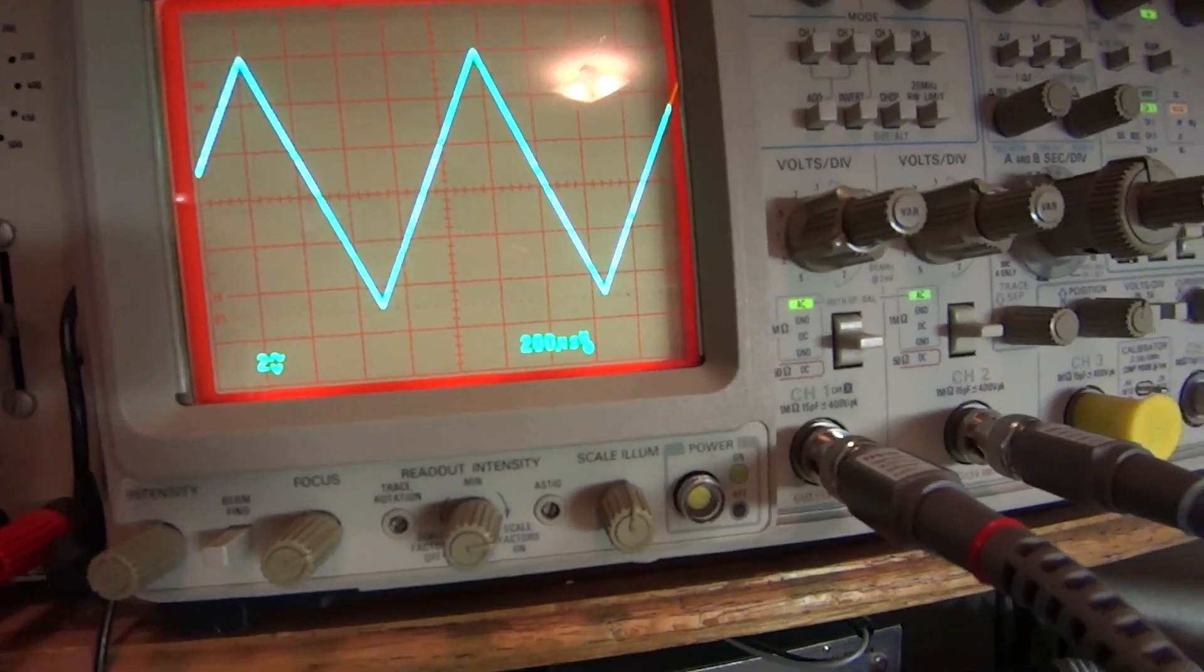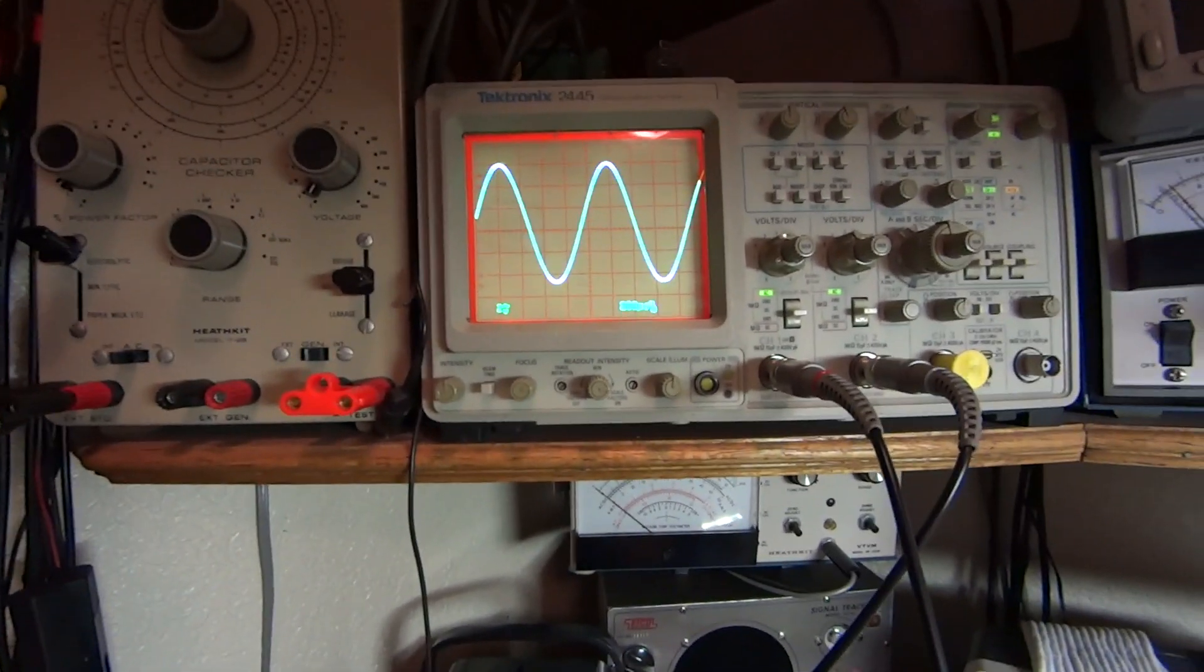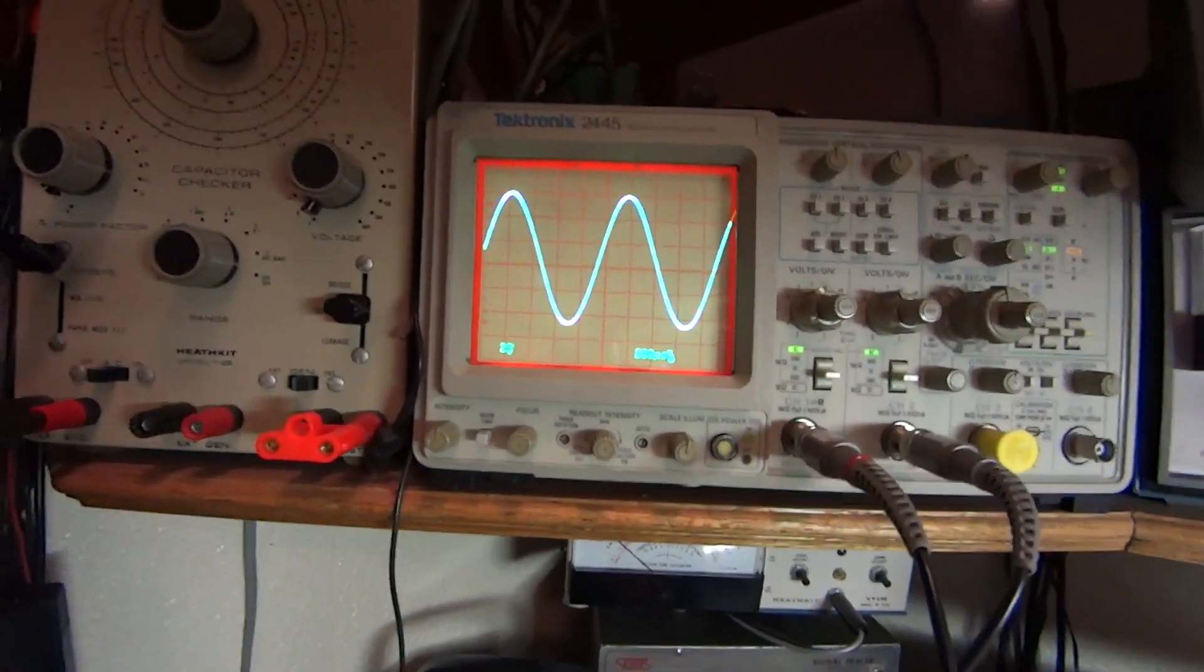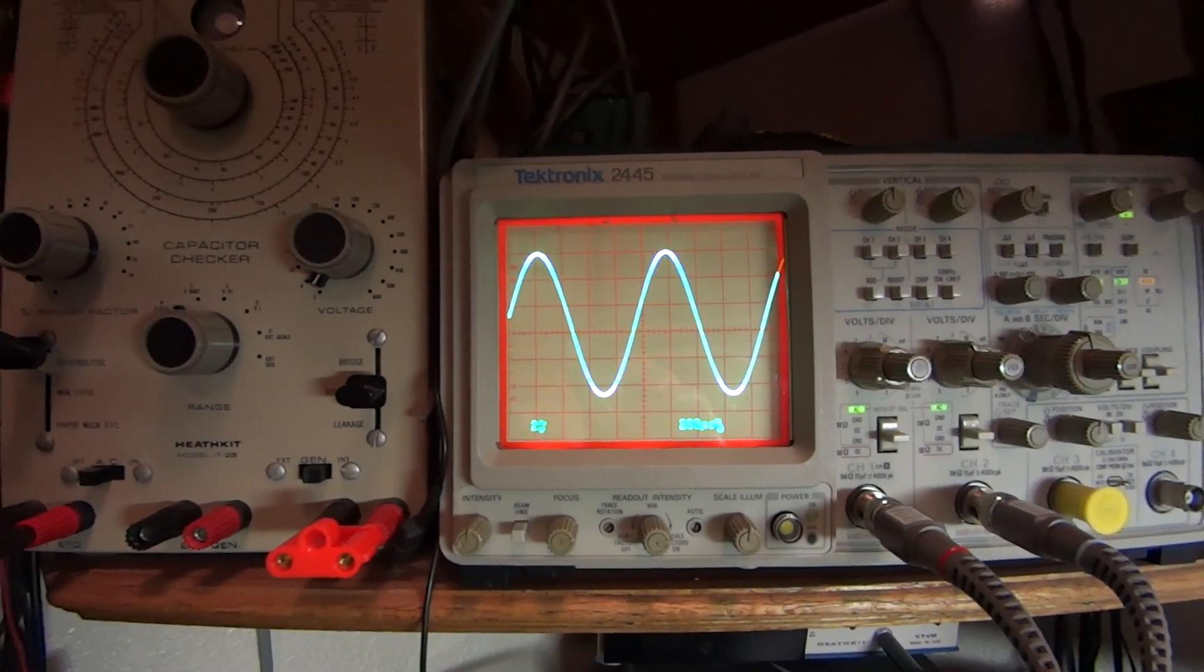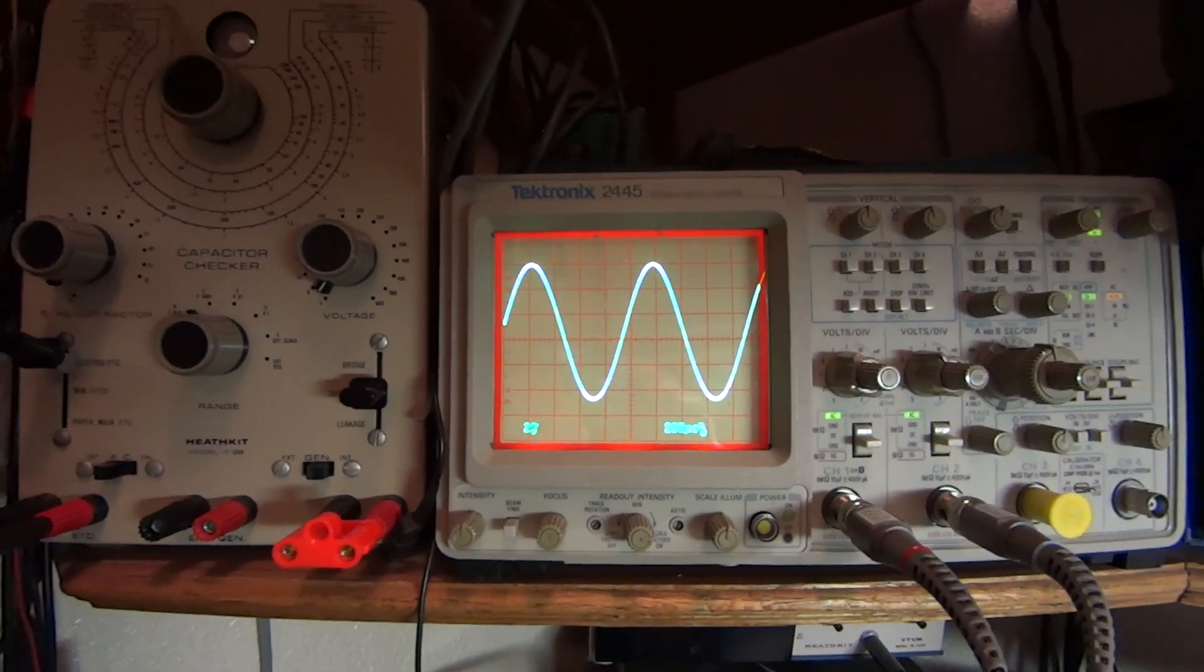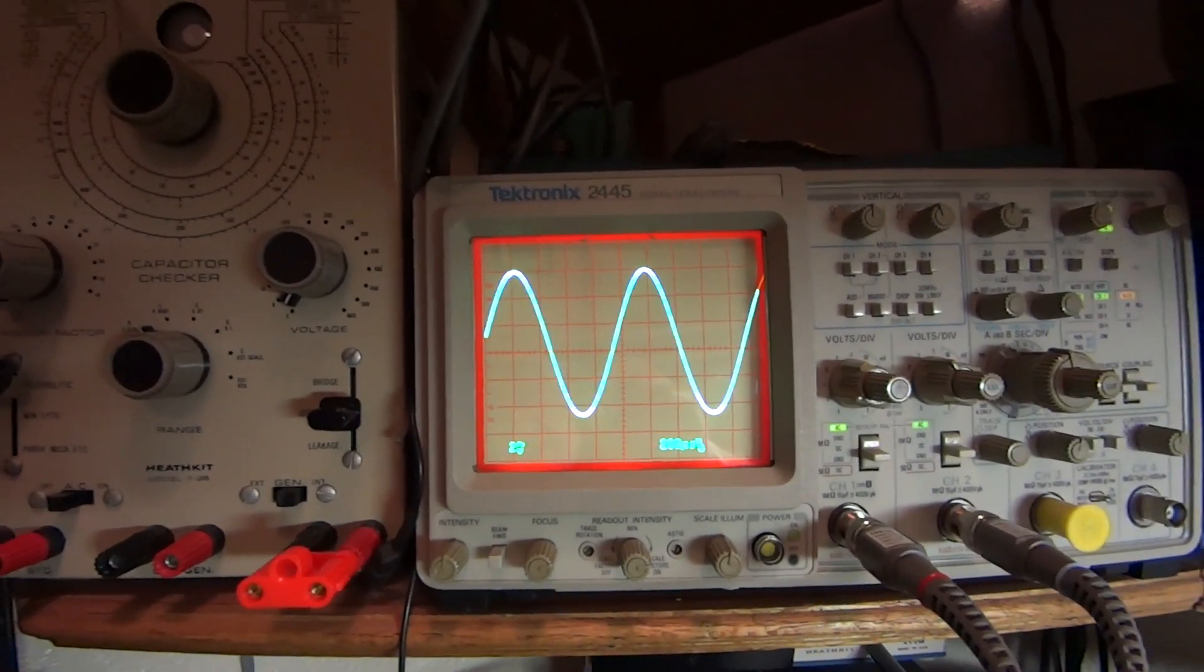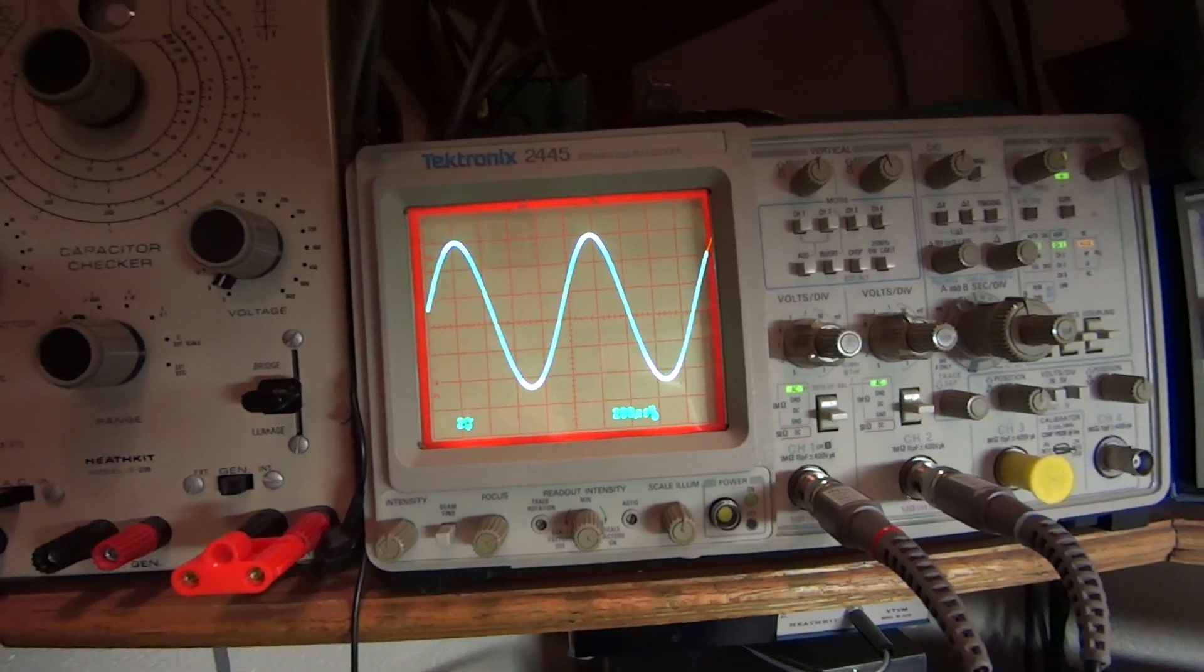So this thing is working really nice. There are a lot of other functions that this will do and it is a function generator. It will sweep and it'll do all of that good stuff. So I'll be testing all of those functions, but for all practical purposes it looks like we got that hundred kilohertz oscillation out of this power supply by replacing those two capacitors. And now we've got a surplus function generator that's a real nice signal generator, real nice function generator. Does more than a signal generator will.